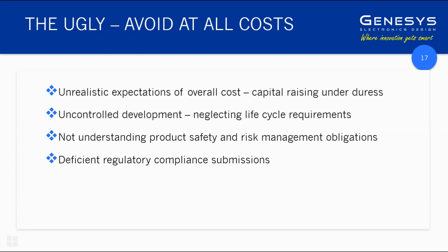And if you don't do that, you simply can't backfill or retrofit later. And so really it causes a great deal of grief not starting with the so-called design controls right at the beginning of the development. Yes, and you may as well explain these last 2 points because they're all sort of tied up with that, isn't it?